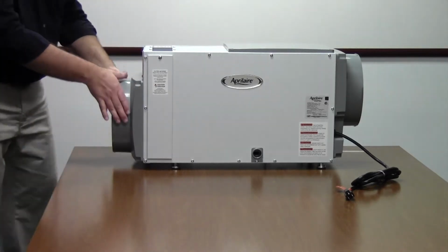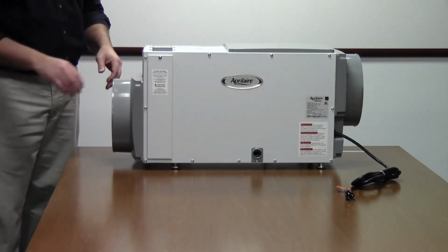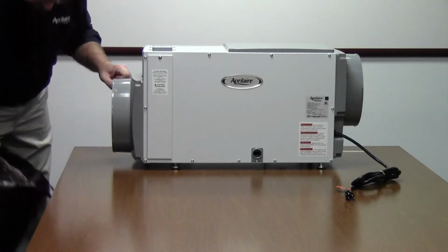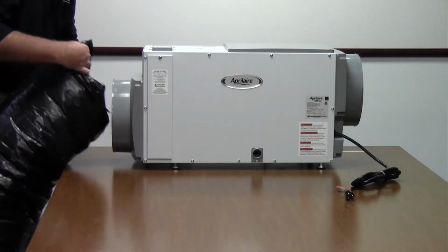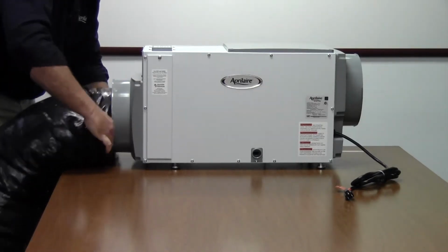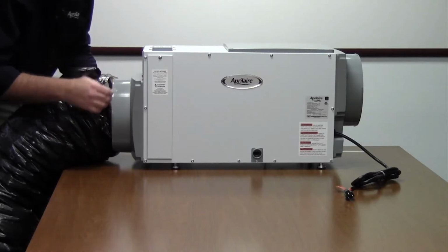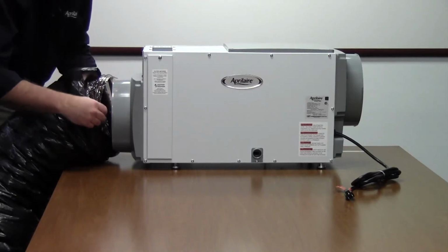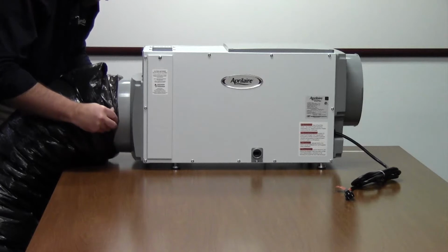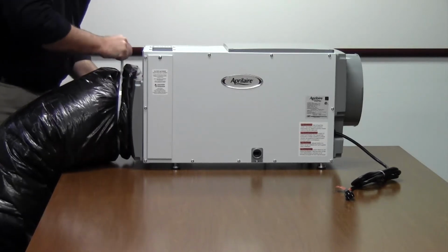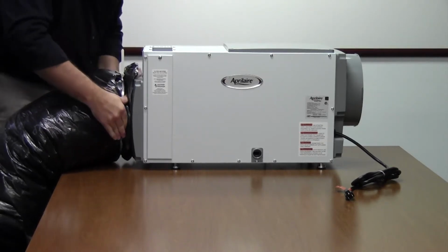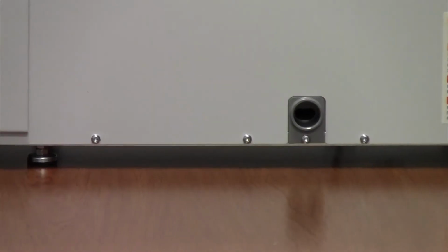Okay, again, these units are designed for flex duct or for hard pipe. So we can just take some standard flex duct and we can attach it to the unit. I did not show on there, but we do have little retainers right here that will help hold that flex duct on there with a zip tie. Now let's talk about the drain.